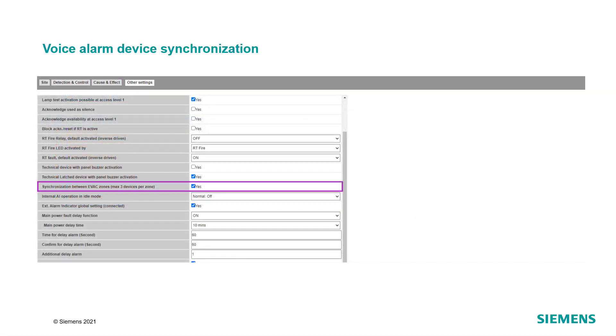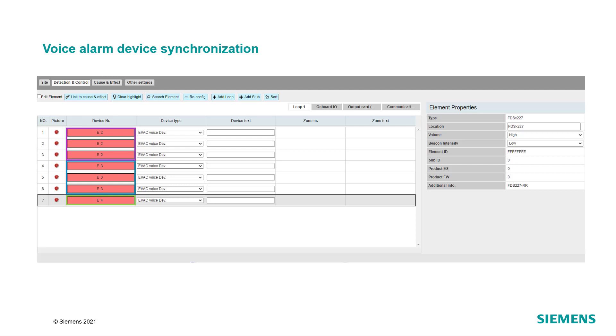For the synchronization of devices with different device numbers, activate the checkbox Synchronization between Evac zones in the Other Settings tab. Please note that a maximum of 3 voice alarm devices should be assigned to the same device number in the Detection and Control tab to ensure the synchronization. The panel supports a maximum of 64 device numbers if this synchronization method is used.